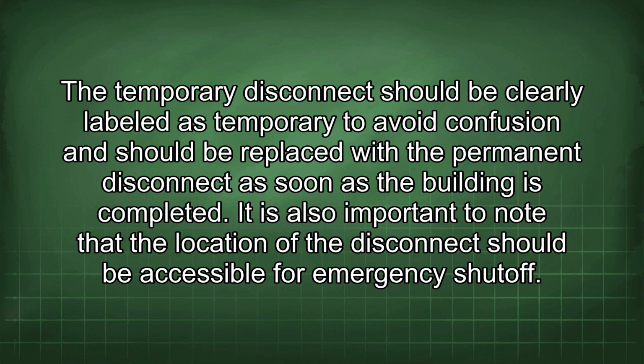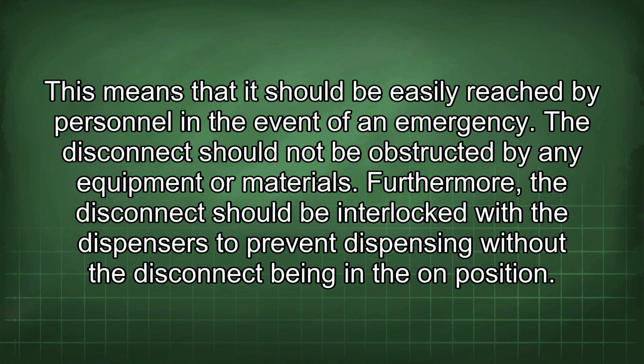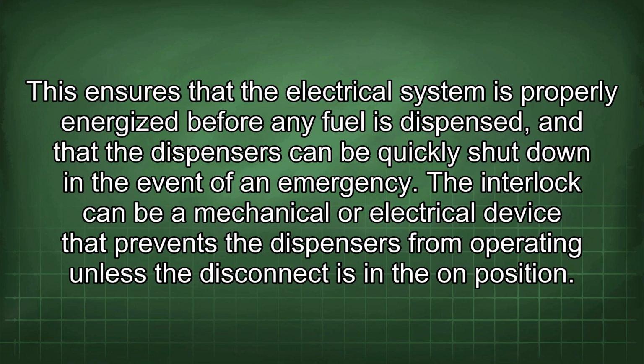It is also important to note that the location of the disconnect should be accessible for emergency shutoff. This means that it should be easily reached by personnel in the event of an emergency. The disconnect should not be obstructed by any equipment or materials. Furthermore, the disconnect should be interlocked with the dispensers to prevent dispensing without the disconnect being in the on position. This ensures that the electrical system is properly energized before any fuel is dispensed, and that the dispensers can be quickly shut down in the event of an emergency.